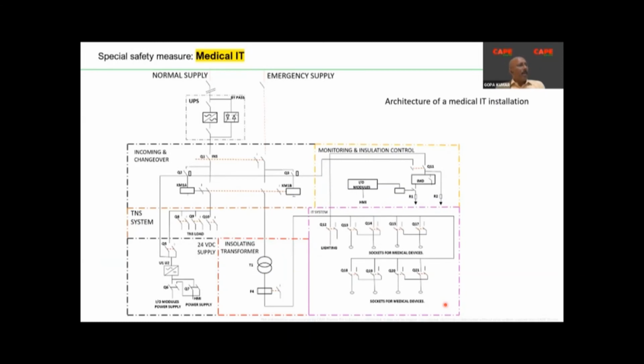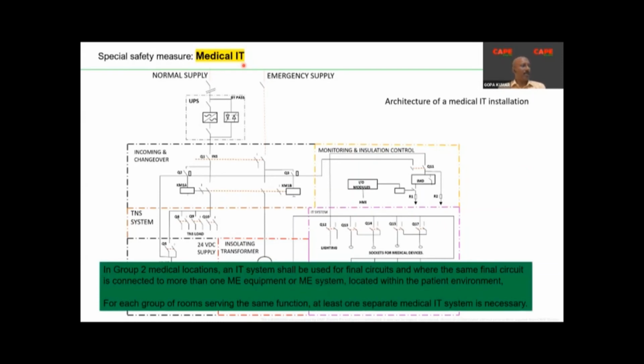Medical areas are classified into Group 0, Group 1, and Group 2 locations. In Group 2 locations, the patient is connected with biomedical equipment internal to the skin, or the biomedical equipment is bypassing the skin and connected to internal organs, as Dr. Lallu showed in a picture; there are several pieces of equipment connected to the patient's body. So in those areas, tripping of your device is a problem. You are not supposed to disconnect your supply, because if the MCB trips, the patient will be in trouble. So for that area, you are supposed to have a medical IT system, which ensures non-disconnection during a fault. You don't need to trip it. There are other methods to ensure safety in this particular case. This was actually made mandatory in the standard several years back.